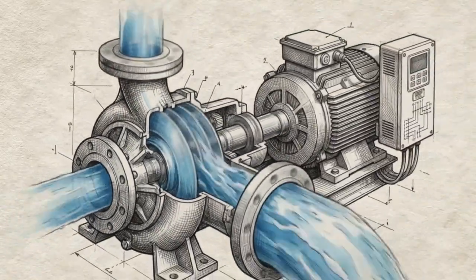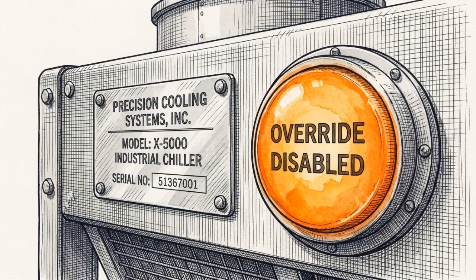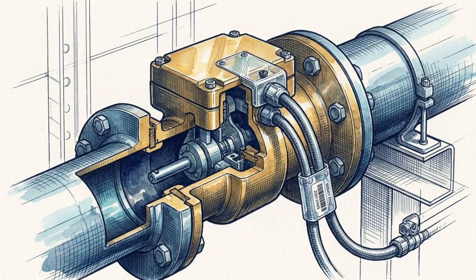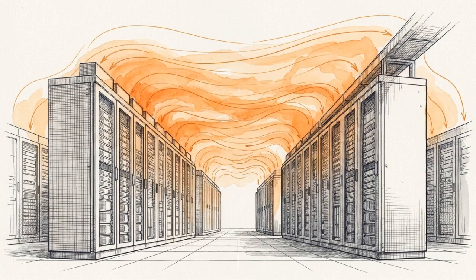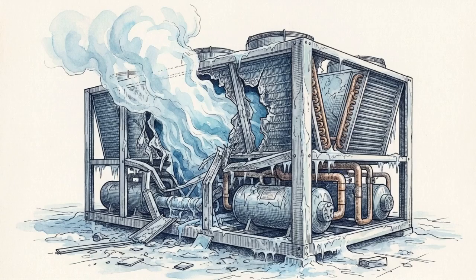This entire sequence strictly adheres to the manufacturer's rapid restart mode. Local mechanical safeties, like low-pressure thresholds and flow switches, are never bypassed or overridden for the sake of speed. Rushing a compressor start without first verifying hydronic flow does not restore cooling to the data halls. It destroys the chiller, releases refrigerant, and permanently compromises the chilled water loop.